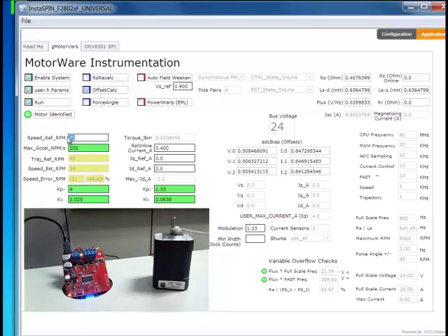So removing the load, let's go lower. 2 hertz. And you're starting to see a little bit of degradation. It's falling off a little bit. You see a little bit in the shaft. The angle's jumping around a little bit, but it's still stable. We can go down to 1 hertz. And it's still moving. It's still stable. If I put any sort of load on it, it continues to drive through that angle.